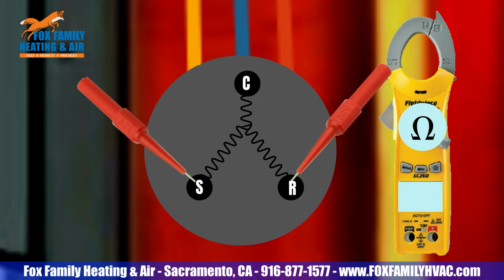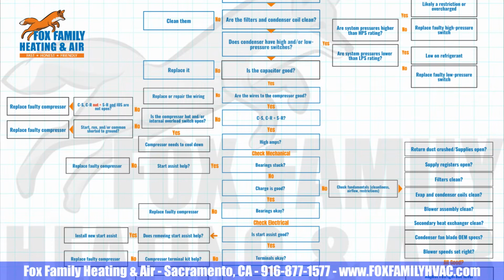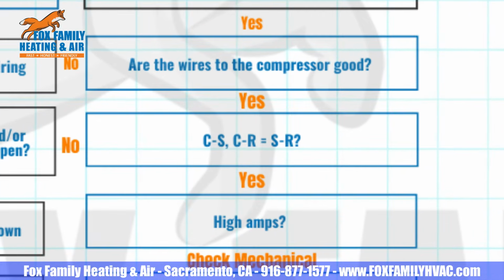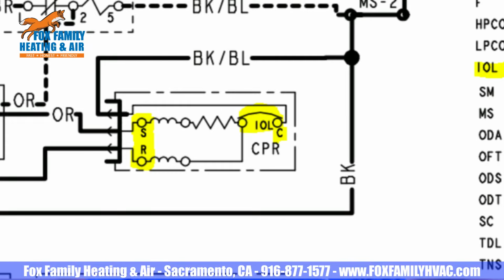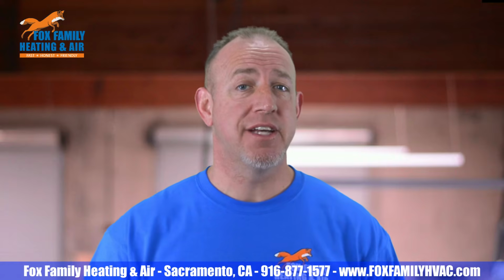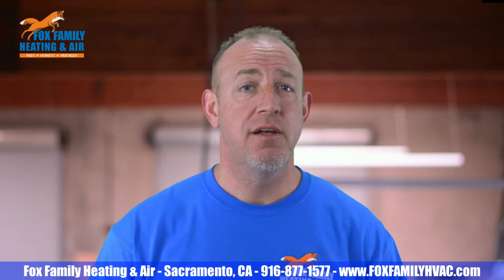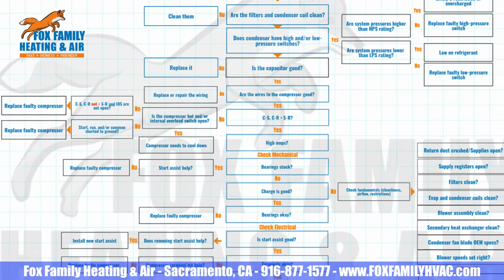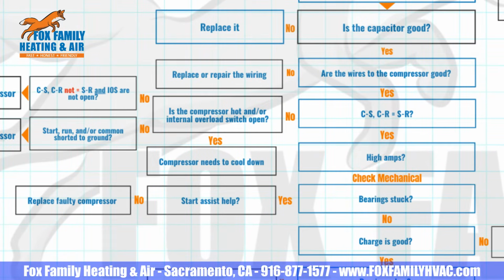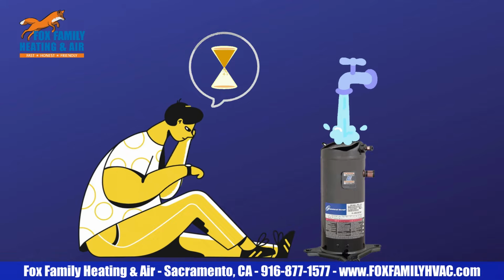Now, does the measurement from common to start and common to run equal or come close to the measurement between start and run? There's an internal overload switch within the windings of the compressor. If you check ohms from start to common and you don't get a reading, and run to common and you don't get a reading there, but you do get a reading between start and run, the internal overload switch is opened or tripped. And if there are any other ways that you experienced technicians know of checking for internal overload with your meter, please let us know in the comments down below. If the limit switch is open and the compressor is hot, it needs to cool down. Of course, with the power off to the unit, get a hose and gently pour water on top of the shell to cool it down.